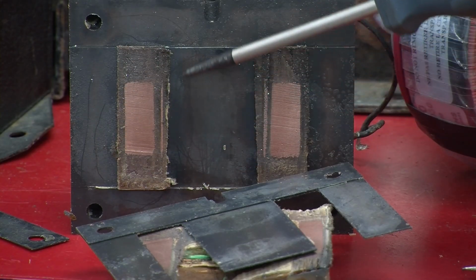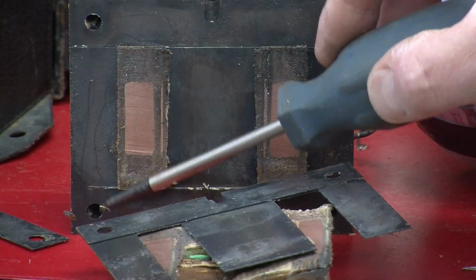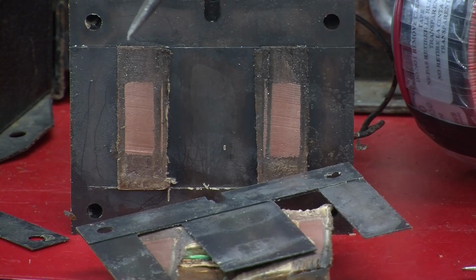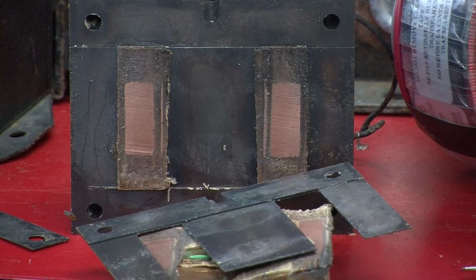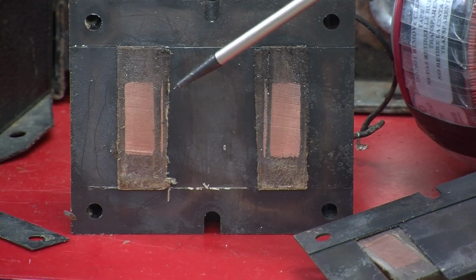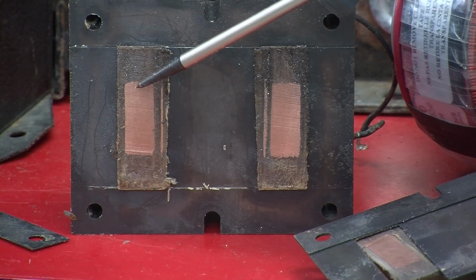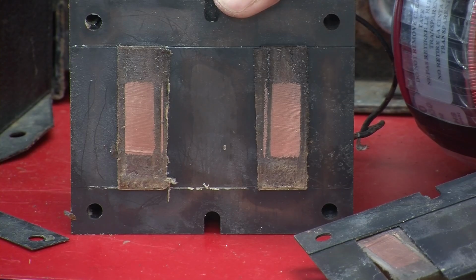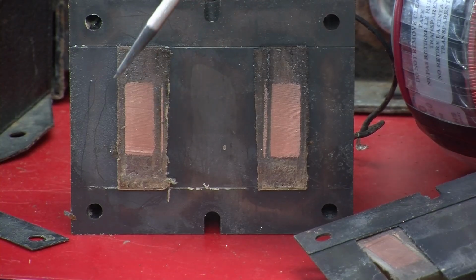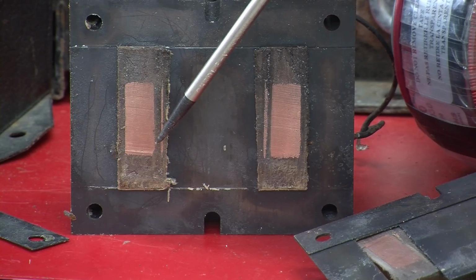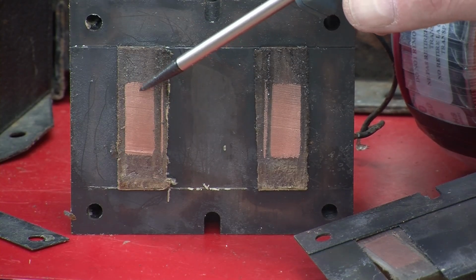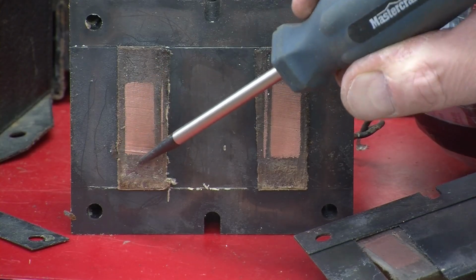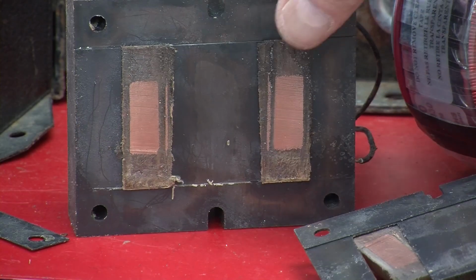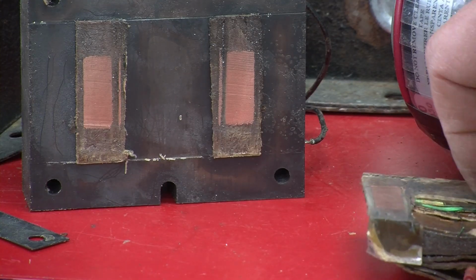That means there is more volume to the core, and that means there is more core loss, more eddy current and hysteresis losses. So for transformer designers, it's really a job of trying to pick the right compromise. You want to have the windings made of wire that is thick enough that you don't lose a vast amount of energy or create a vast amount of heat from the current flowing through those windings. And you also want to try and keep the core as small as you can to minimize the amount of energy that is lost in core losses. And depending on how the transformer is going to be used, you can move the compromise in one direction or the other. That's the basic idea behind transformers.